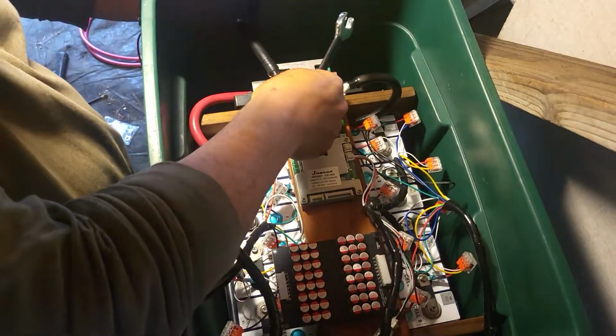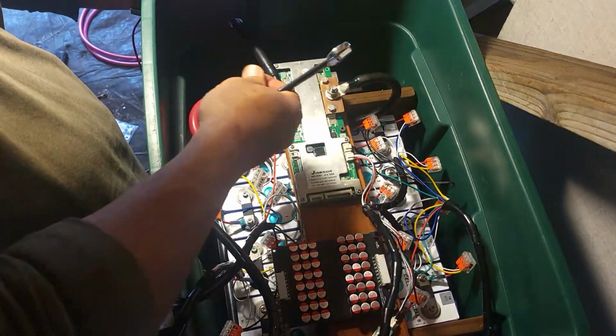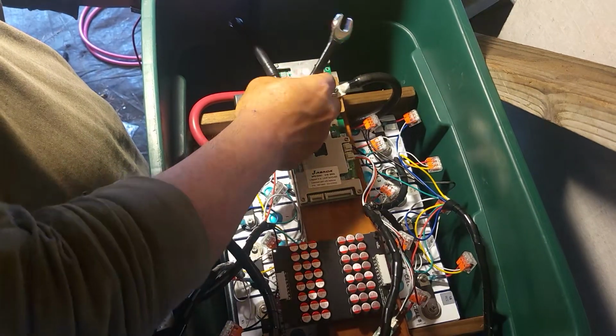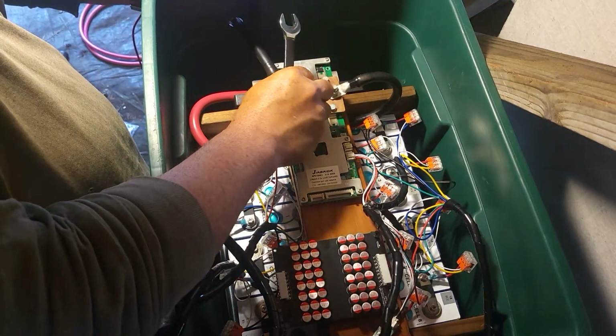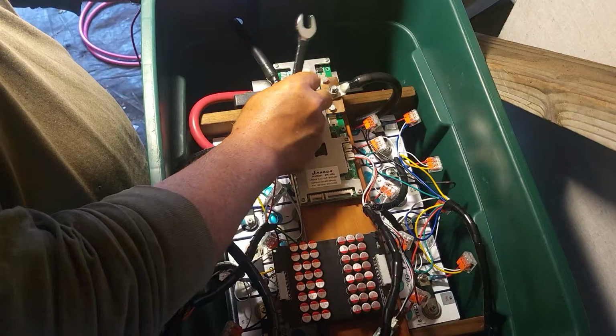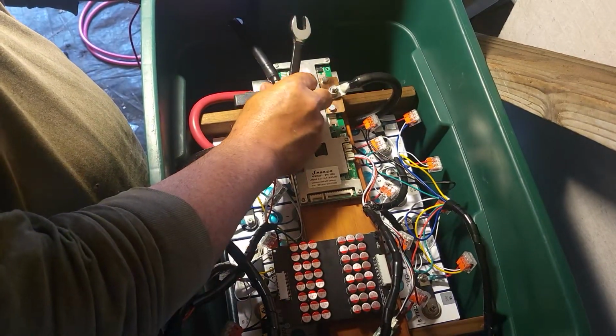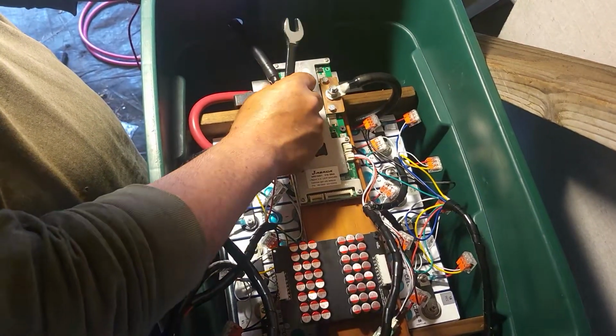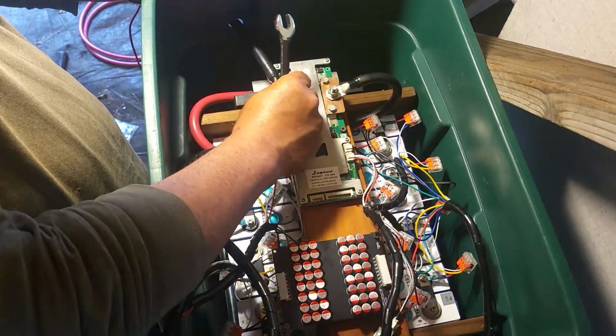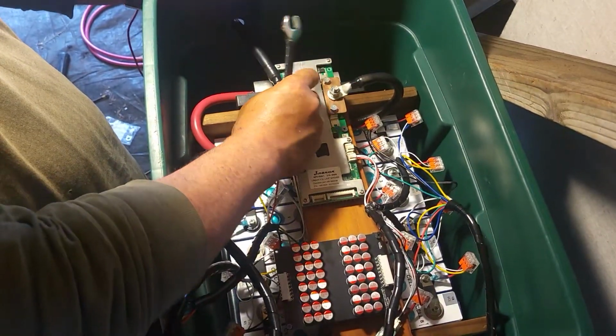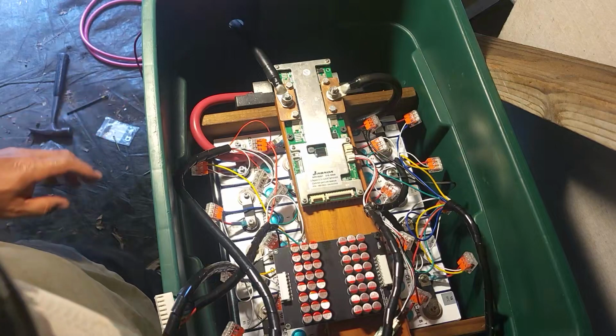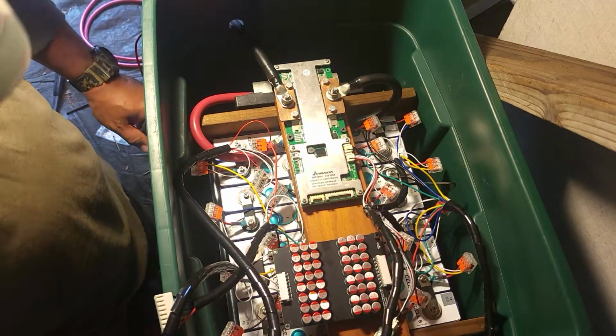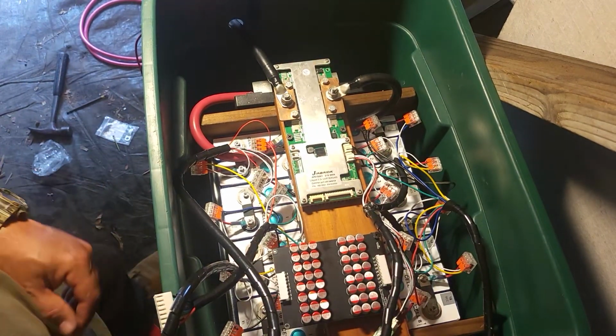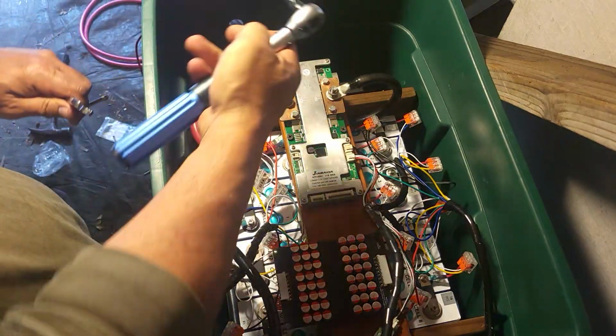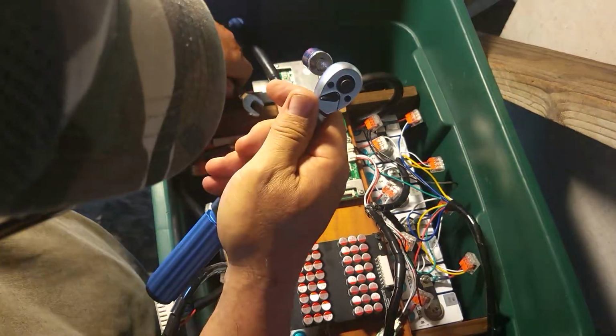Alright, I'm running the negative. I'm going to run the negative lead that we just measured out and put lugs on. This is the battery out that goes to the bus bar, to the inverters, to supply power to the inverters. Right now the opposite end of this lead is not hooked up to anything yet. I'm just installing this on C-.